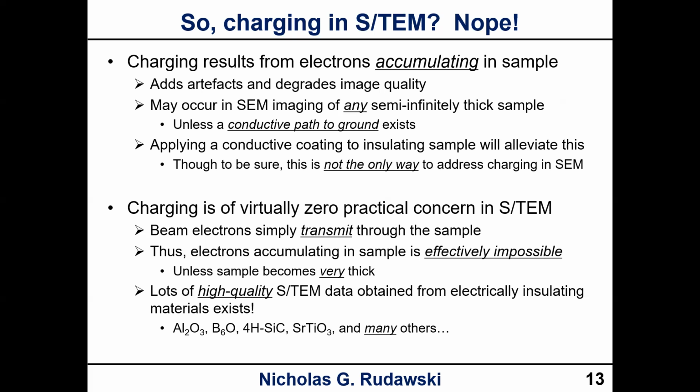There are things we can do as far as the actual scanning that we do in the SEM to reduce the charging, which is a video I hope to do at some point, because it is pretty cool to see how this can work, or at least improve the quality of your images. And there's also things like variable pressure or environmental SEM, which are used also as ways to help mitigate the charging.